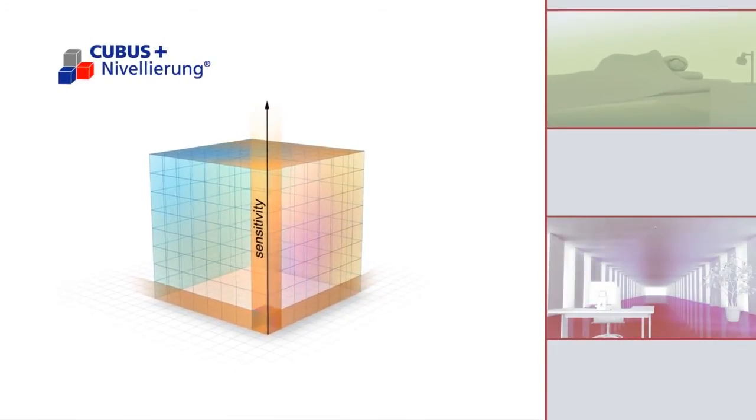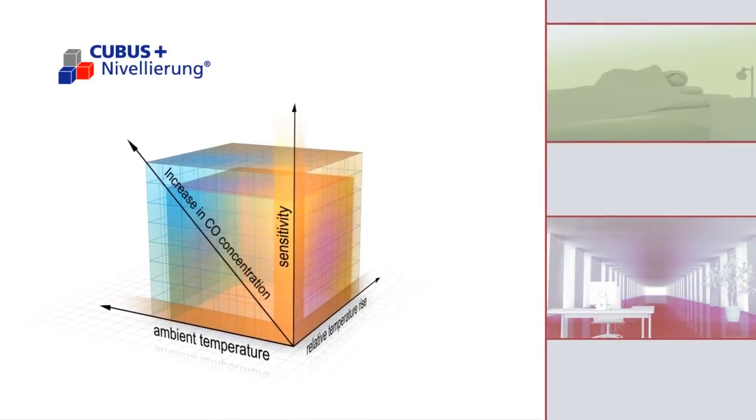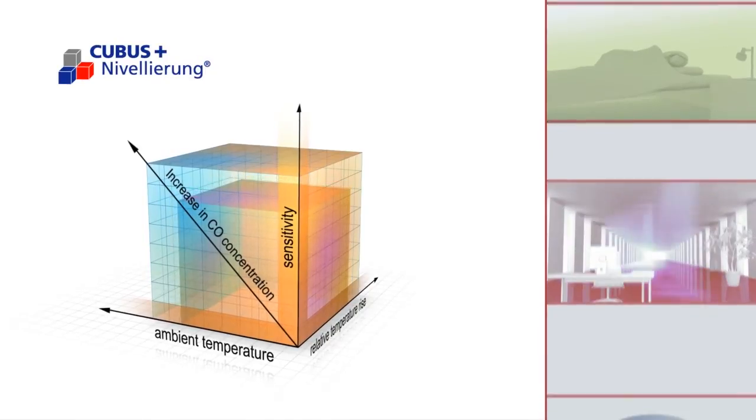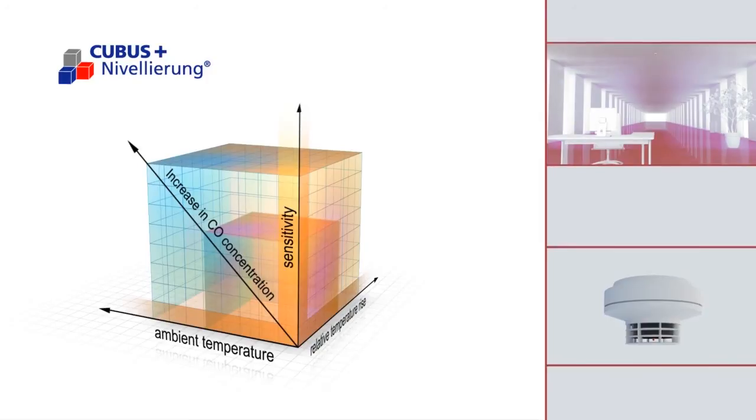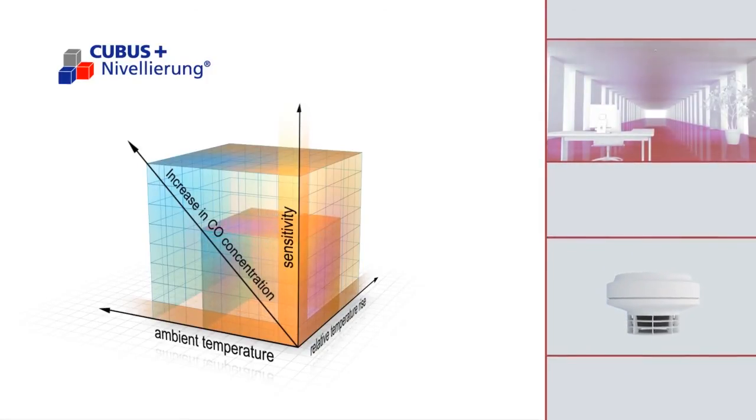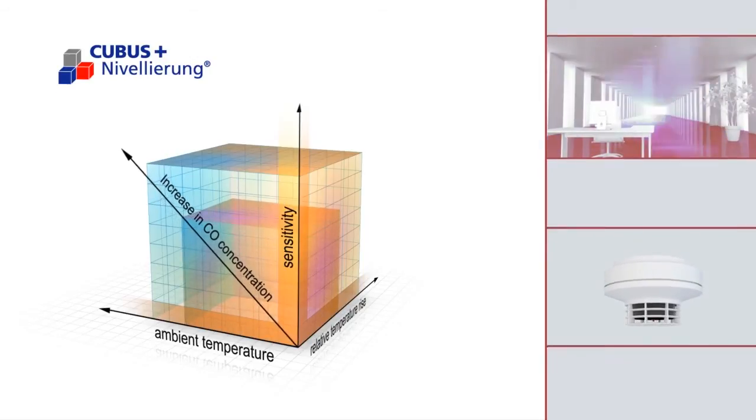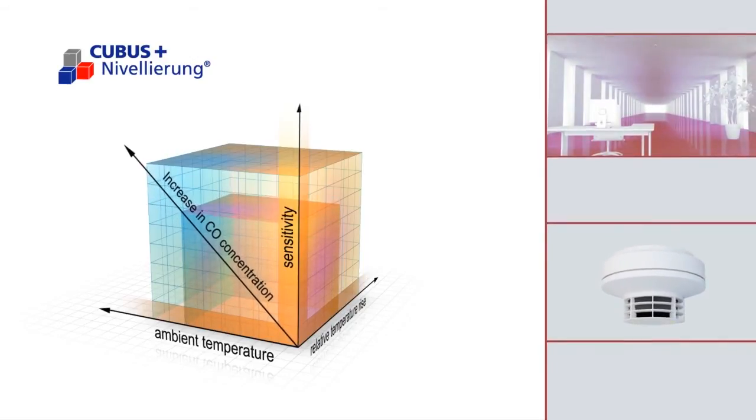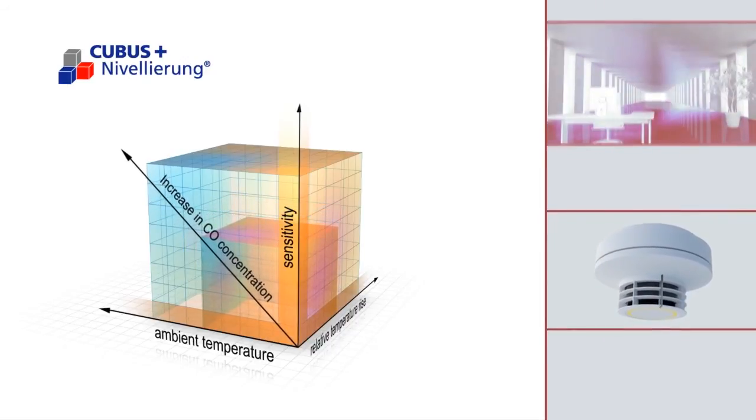In addition to measuring the ambient temperature, the CMD533X also measures the carbon monoxide, CO, concentration, and therefore adapts even more optimally to its surroundings. Depending on how the ambient temperature and CO concentration change, it then sets the optimum sensitivity of the smoke sensor. Consequently, it guarantees quick and safe detection.